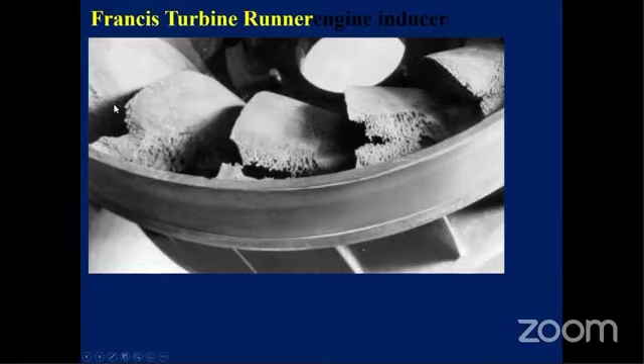This is an example: a Francis turbine runner that has experienced cavitation. You can see the cavitation has eaten through, almost completely, the turbine runner blades, made of cast iron in this instance. Notice it has a crystalline-like appearance, damage I'll reference again later.